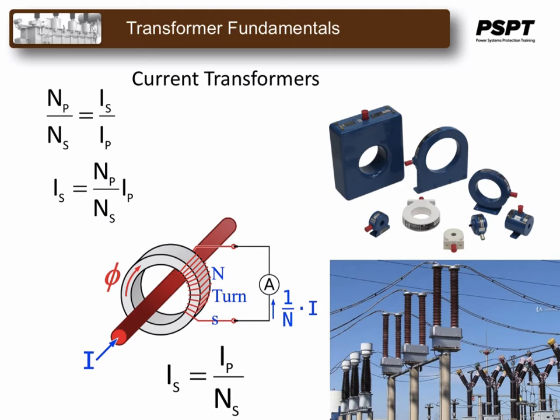There is a unique problem encountered with CTs. In order to magnetize the core of a current transformer, a certain amount of excitation current is required. Part of the current induced from the primary is used to accomplish this. Since the induced current represents the current flowing in the load circuit, the meter's current coil will be influenced proportionally by the load current minus this excitation current.